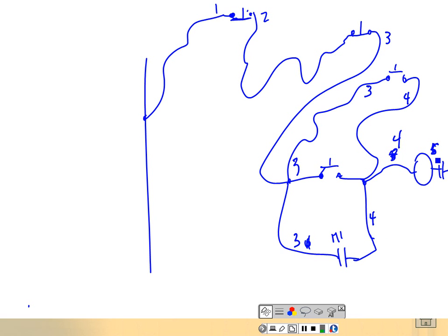A lot of times, they might not exactly go in sequence, but they usually don't go back, they might just skip over some numbers. And why they do that is they might have varying connections of that control. It's the same control, but this company wants this, and this company doesn't want that. So what they do is leave the wire numbers the same for all of them. Does that make sense? I've never seen them go backwards, but I have seen them skip a few numbers. The only thing I can understand is that they have several variations of that same control circuit.